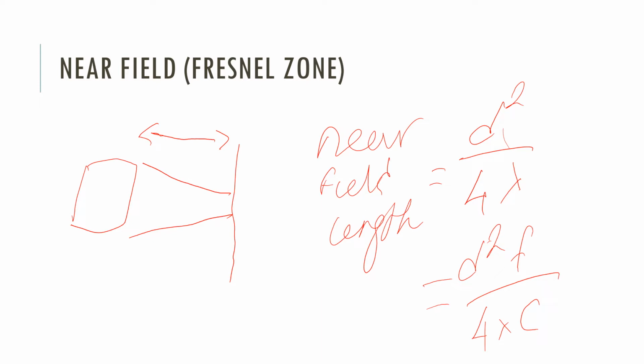Okay, and this is all up to this. This is the distance from the transducer to the focal point. So remember, unlike focused beams where you have a focal zone, here we're talking about an unfocused beam where all we have is a focal point, and from here it actually starts to diverge.